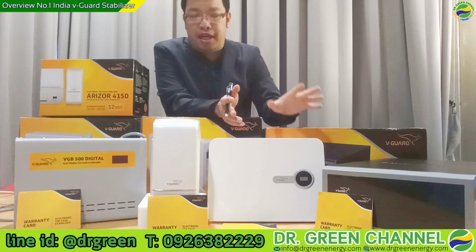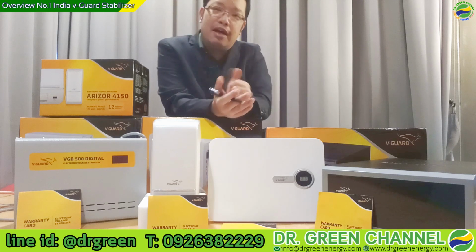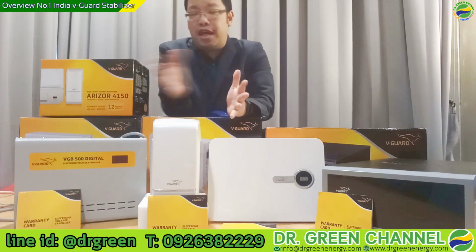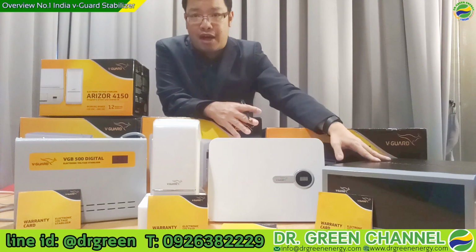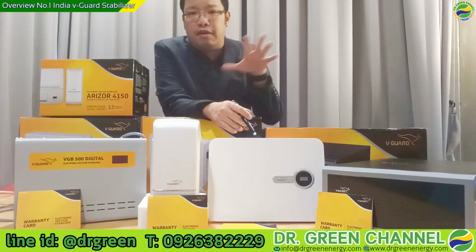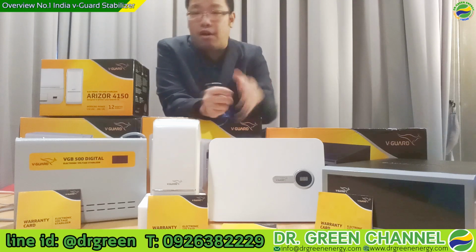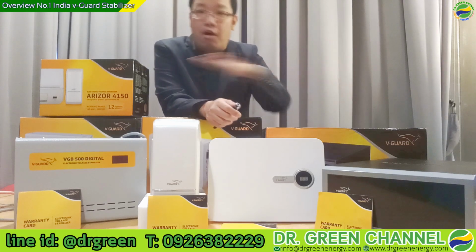So it might be one room, you put one aircon stabilizer, or you put one stabilizer to manage the other loads in the room, for the main lines, for example. Right. So from here, you can see we have stabilizers with a very rugged design, and safety is very important. A good safety feature, for example, the first one is the high-low cut incoming voltage protection. So in the case of too high or too low voltage coming in, the stabilizer will have to manage or cut off.